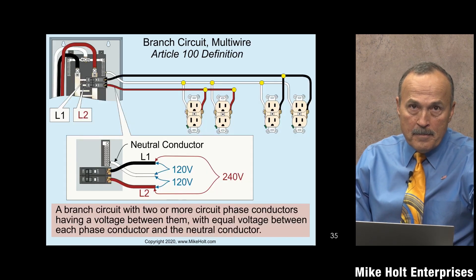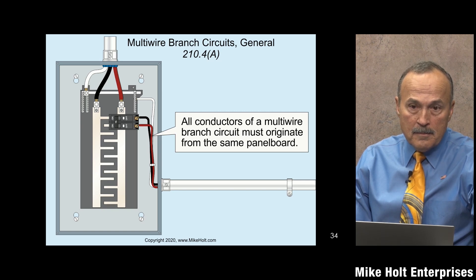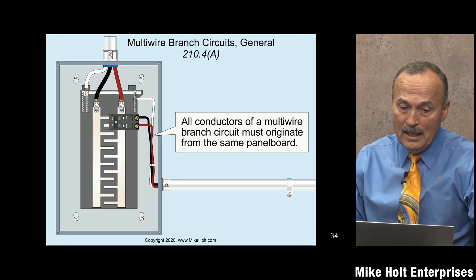The reason this rule matters — especially for new electricians — is a scenario where you have two panels side by side, each with one space left. Someone gets creative, shares a neutral, and puts one circuit from each panel. You're tracing wires through conduit and junction boxes only to find one circuit came from this panel and one from another, because both panels were full. It's creative but it's a code violation.